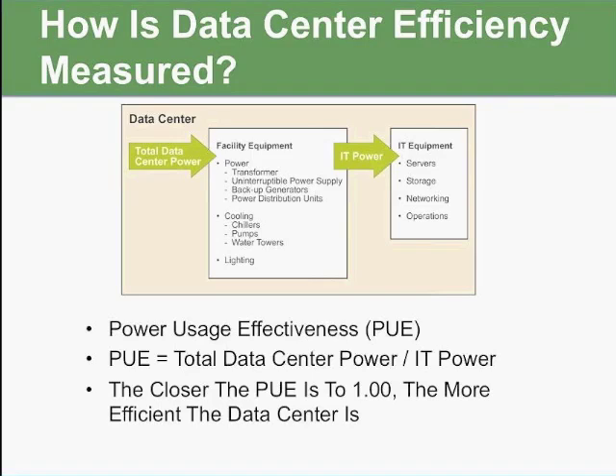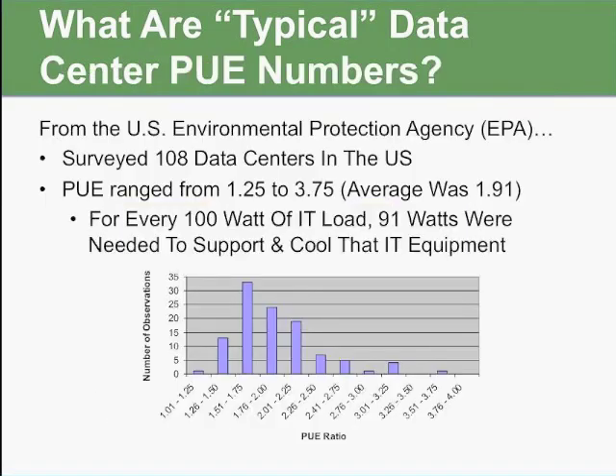It's a lot easier to do this with a dedicated data center building, but even within commercial buildings, which is where basically 99% of the data centers are, these small server rooms, you can also utilize this technique to figure out how efficient you are. As I said, the closer you get to 1.0, the better you are. The EPA a while back did a survey of over 100 data centers in the U.S., and they found a wide variety of efficiency, everywhere from 1.25 up to almost 4, with the average being 1.91, which means that for every 100 watts of IT load, you need 91 watts of cooling and support load to support that IT equipment.